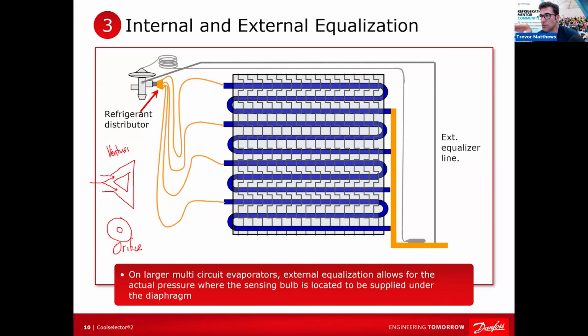Yeah, definitely. That's huge. If you don't have another valve, and I've done it myself, man, and it's an internal, just add the line, drill a hole in it, make sure you don't get any copper in the line. The big thing is that these can plug up if you don't, once again, use nitrogen while you're brazing. So you've got to purge, because these can plug up.